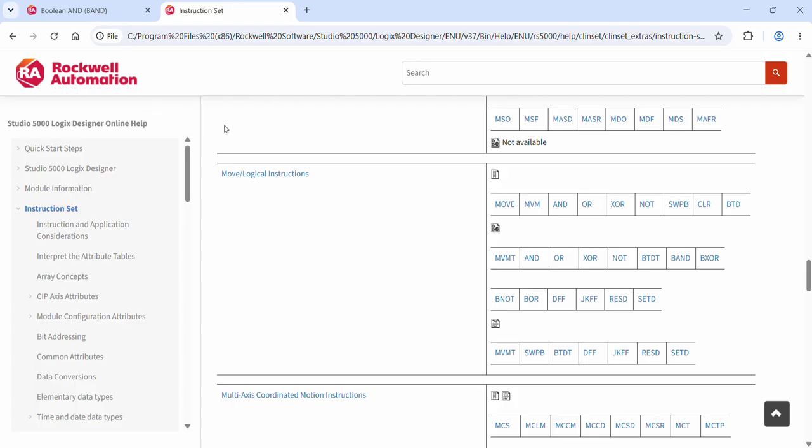Yeah, that's this category. With ladder diagram, you have XOR, but it operates on the integer. In FBD, you have the same thing, XOR, similar to this, but they also have the addition of the BXOR. So they allow you to directly operate on the Boolean. That's what the B represents. So that's what we're going to use for this video.